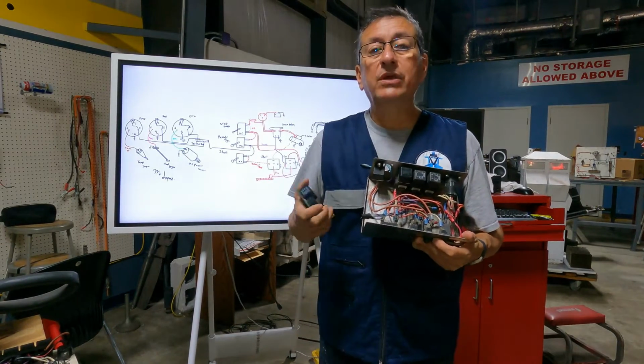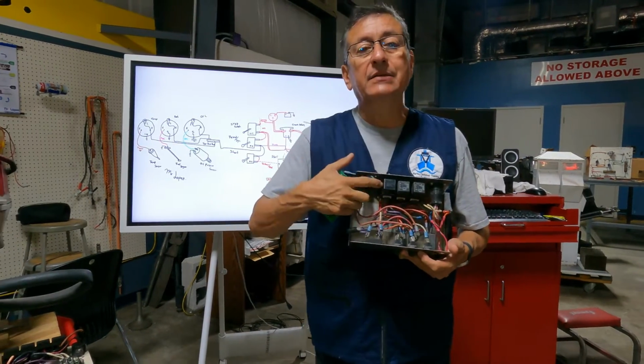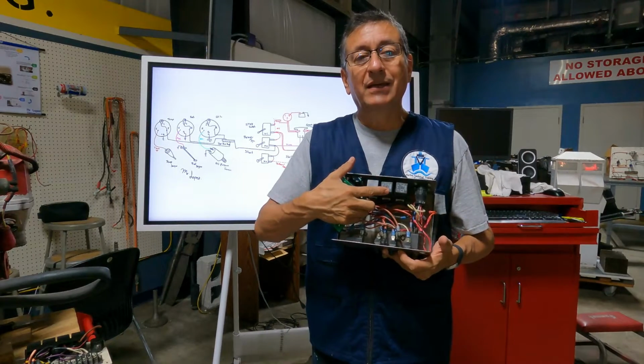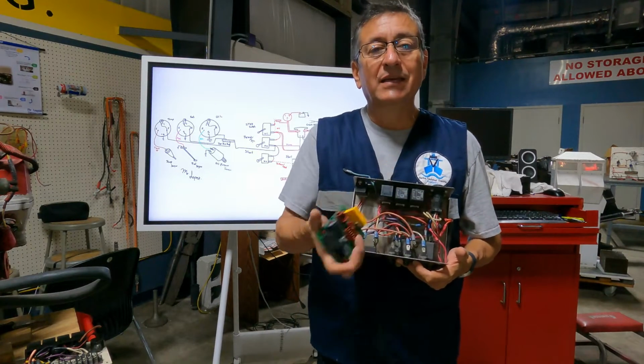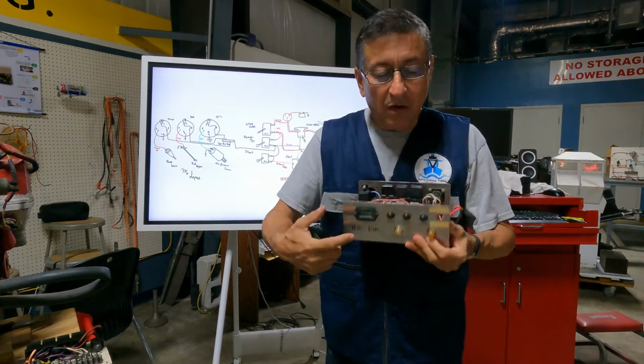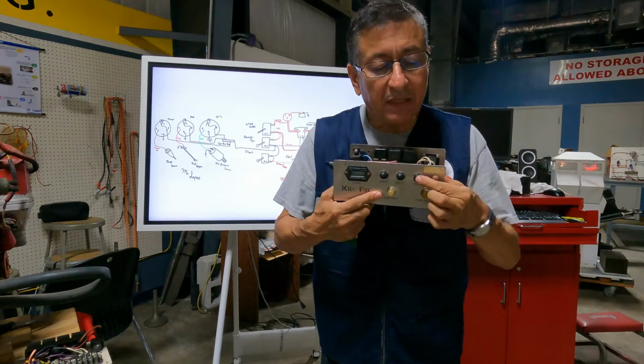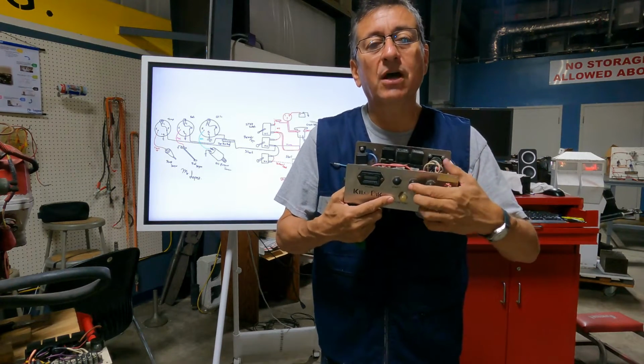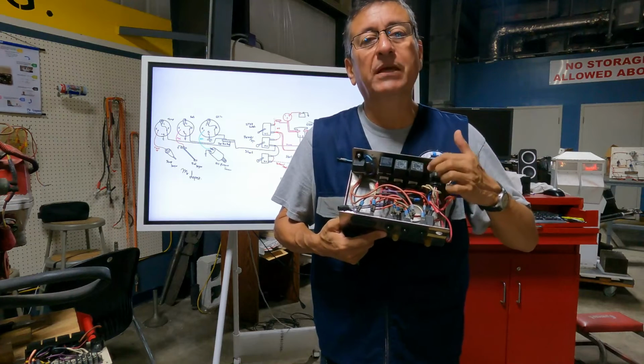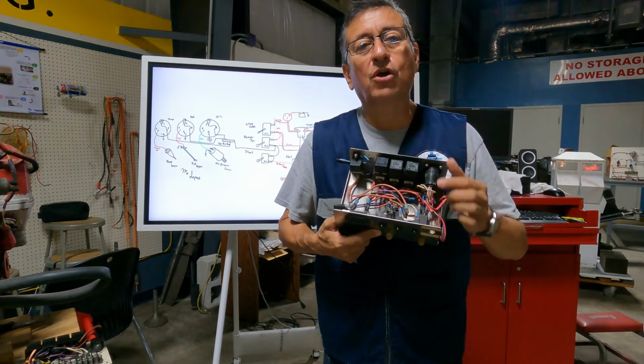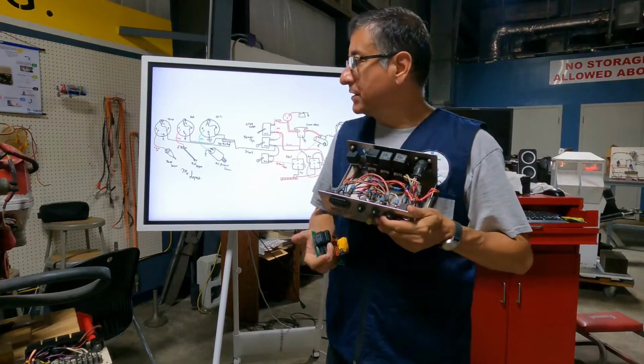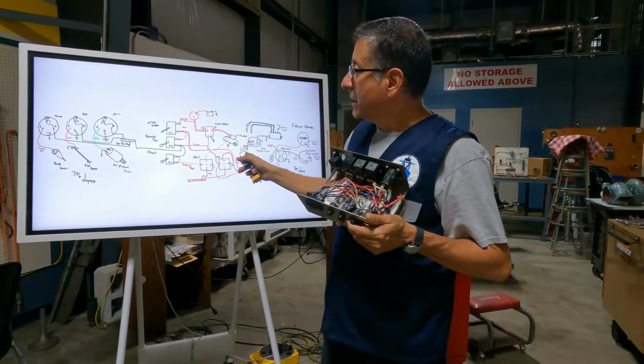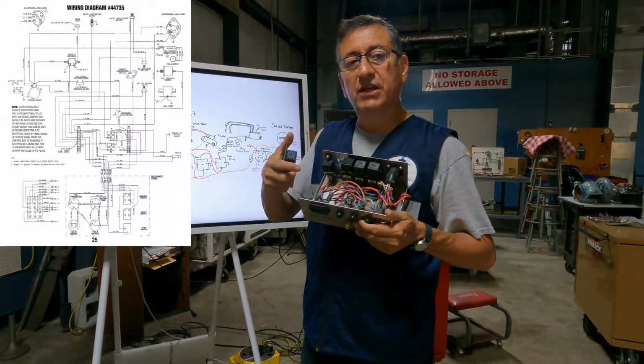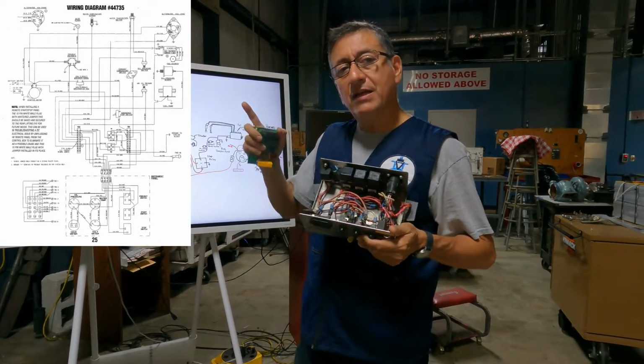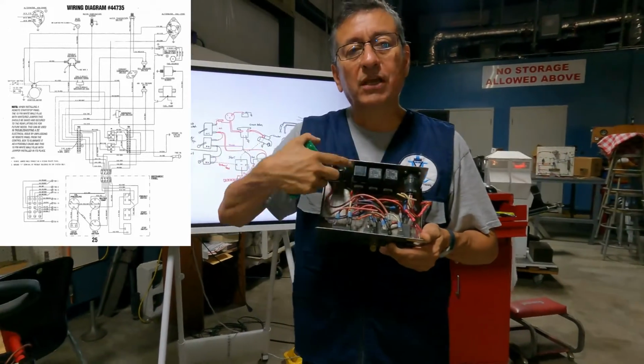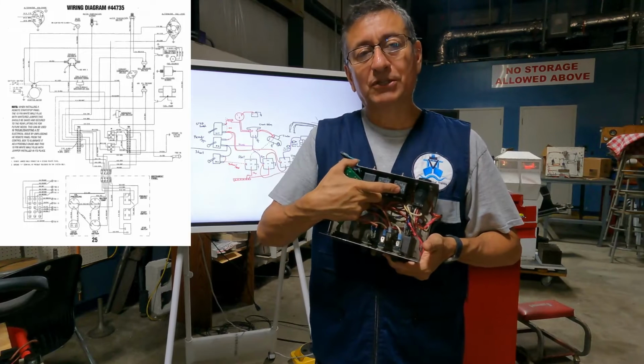I want you to easily identify the relays: the start relay, the run relay, the preheat relay. Verify the connection between the momentary switches for start, stop, and run with respect to the relays and the color codes. Print the wiring diagram of your specific generator and verify if it matches the wiring in your control box.